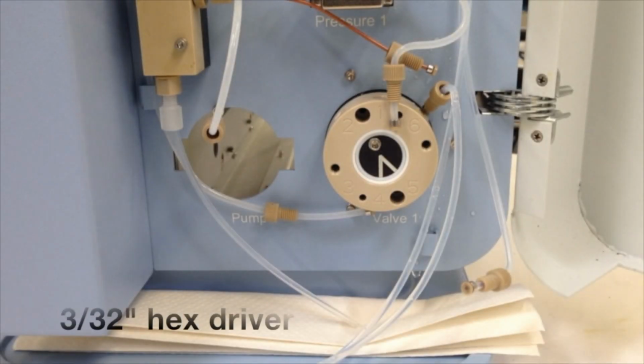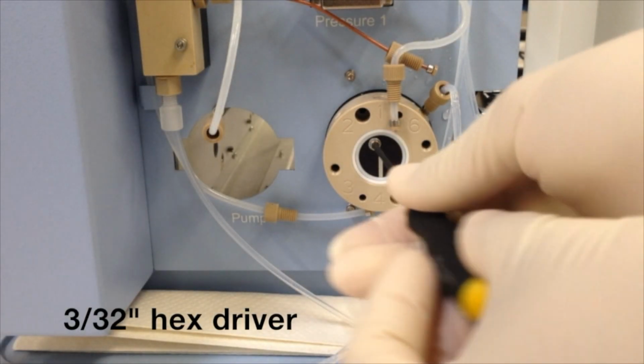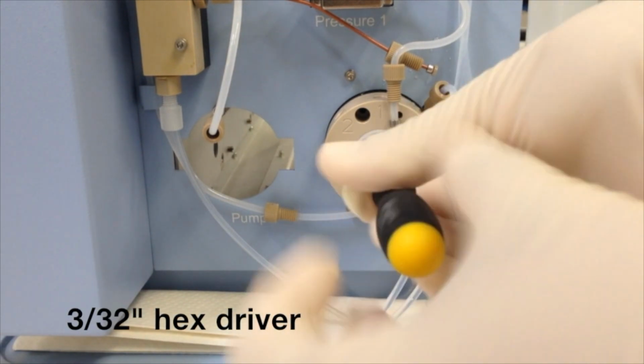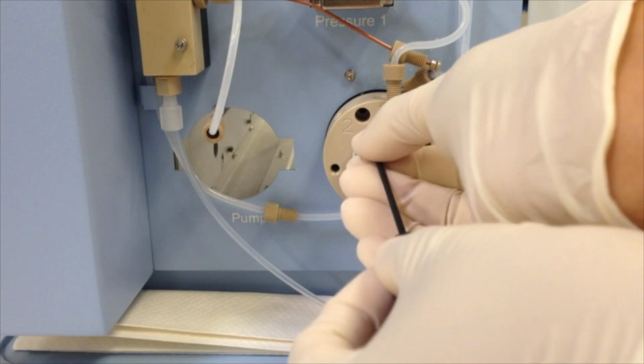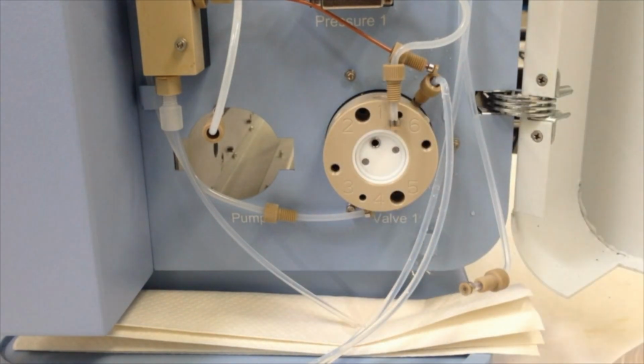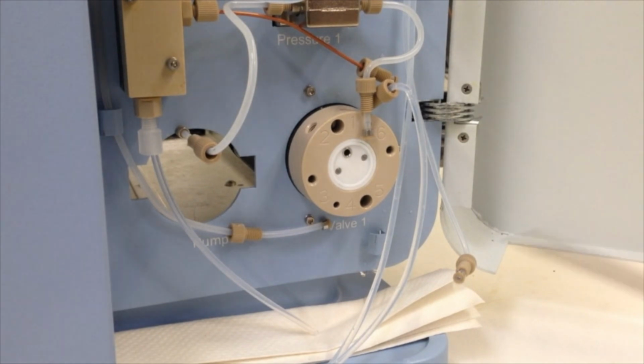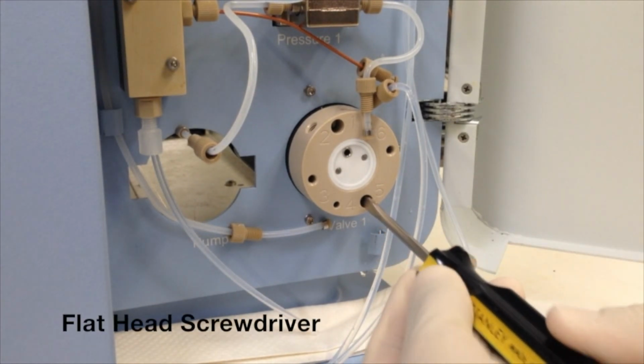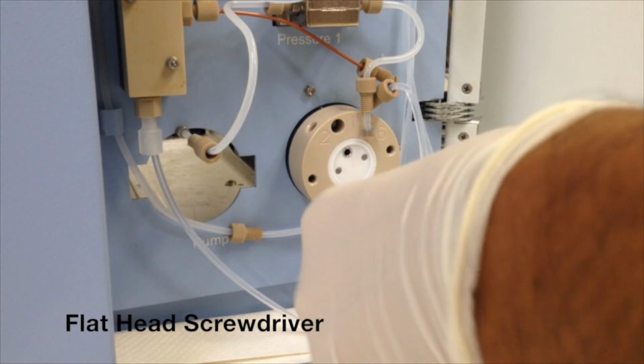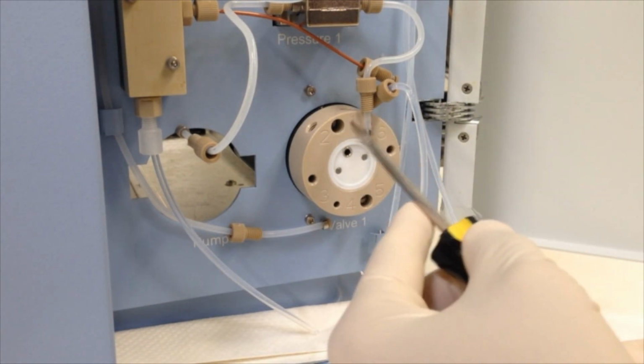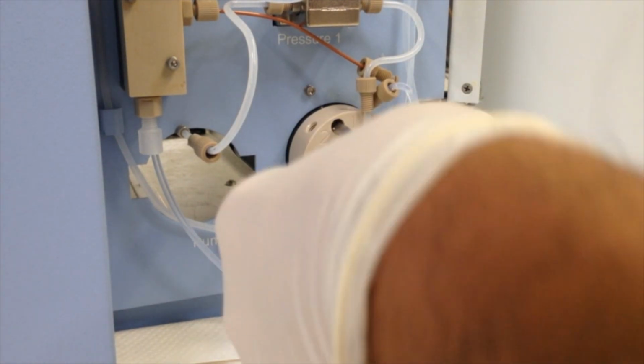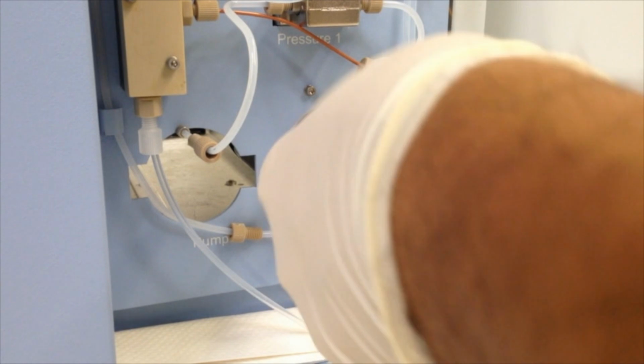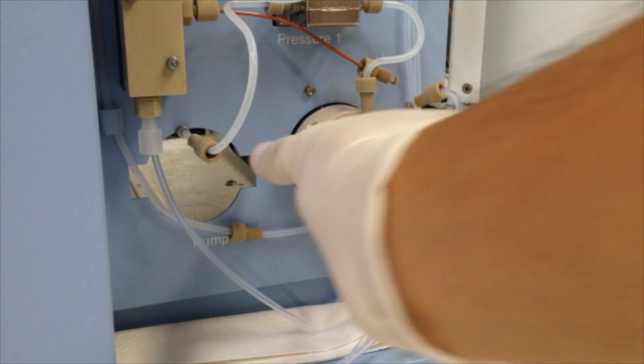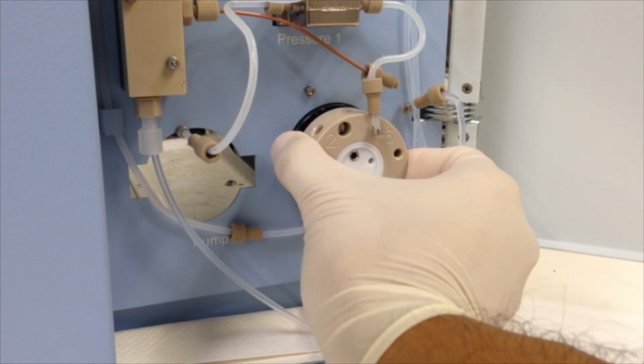Use a 3/32" hex driver to remove the valve indicator plate. Use a flathead screwdriver to remove the two cap screws that secure the valve face to the valve motor. Now pull the valve face completely off.